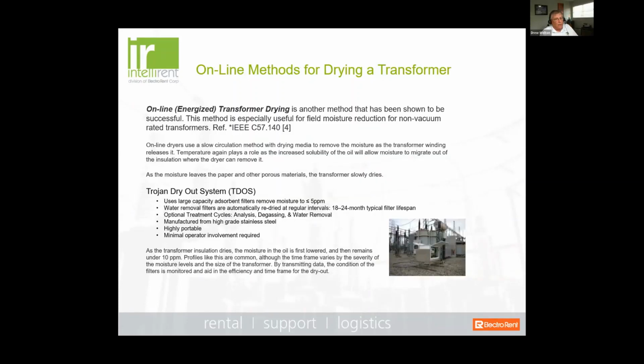Okay, now, what happens when we do determine that we have a wet transformer and the insulation needs to be dried? There are a lot of different types of methods. Okay, you can bring in a processing truck while the transformer's offline and do a hot oil spray. And I've had some people tell me, well, I had one guy from Weidmann tell me that trying to use that approach is like trying to raise the level of the ocean with a shot glass.